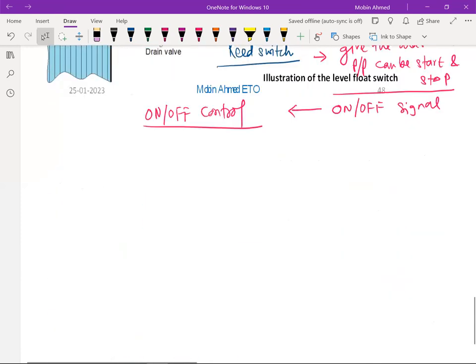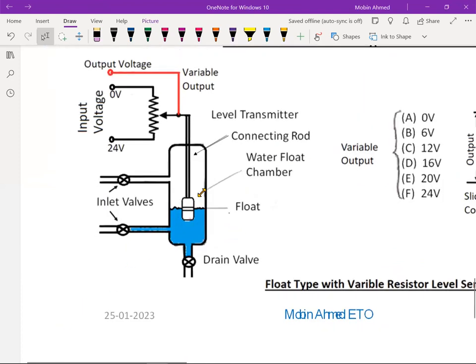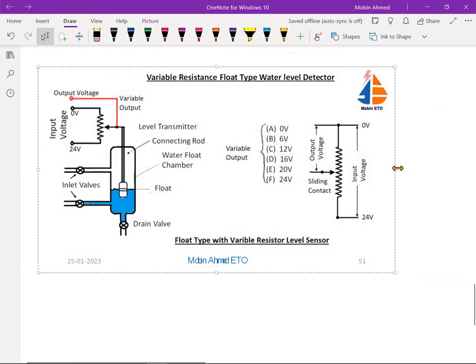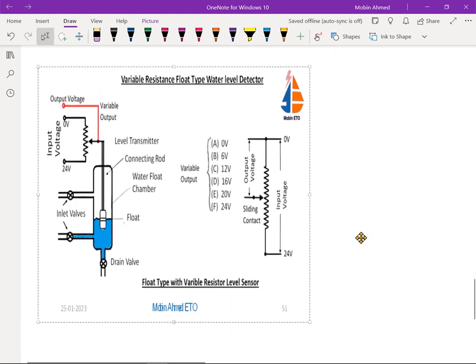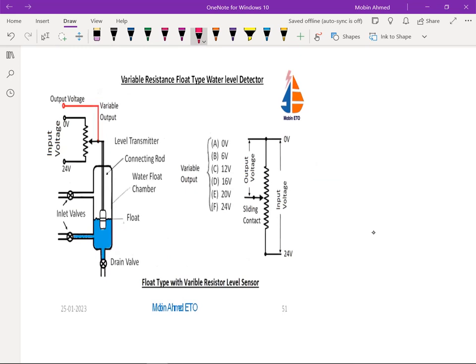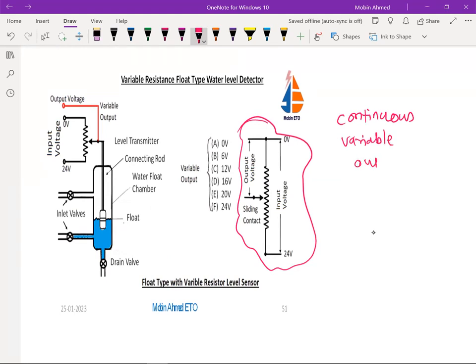Now next we are going to have the variable type, variable resistance float type we are having. So we do have the same arrangement again, only in place of the reed switch, we are going to have the variable resistance. So this is the resistance you can see here. This is the resistance that we are going to have. And from this resistance we can have the output. So there is a variable output from 0 to 24 volt we can have. And if we are going to have a variable output, this is going to give a continuous signal. Remember, it is going to give a continuous variable output.